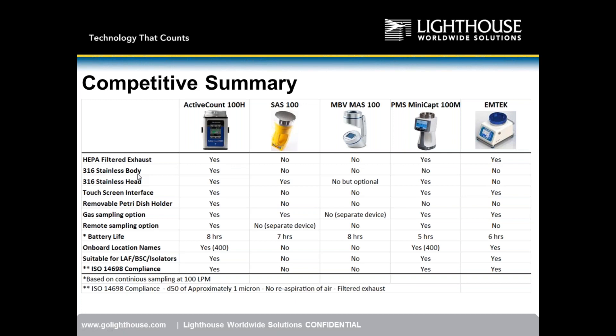Lighthouse and PMS and EmTech have HEPA filtered exhaust. For body construction: we are 316L stainless steel; SAS is plastic; MBV is aluminum; PMS is plastic; EmTek is plastic. Plastic gets micro-abrasions and scratches — potential sources for microbial contamination — and is harder to clean. Our unit ships standard with a 316L stainless steel head; for MBV it is optional and costs more.